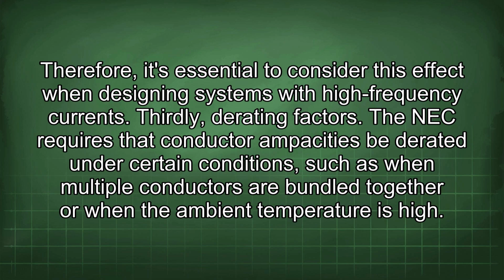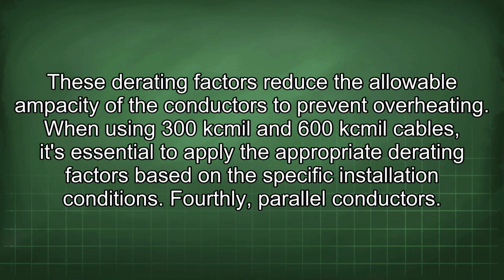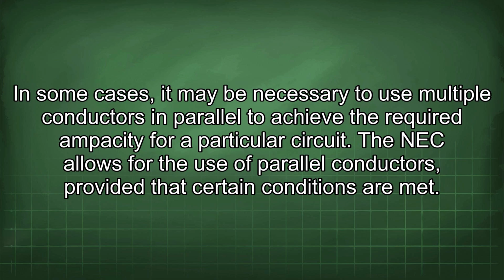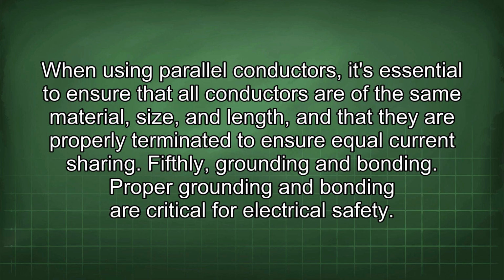Thirdly, derating factors. The NEC requires that conductor ampacities be derated under certain conditions, such as when multiple conductors are bundled together or when the ambient temperature is high. These derating factors reduce the allowable ampacity of the conductors to prevent overheating. When using 300kcmil and 600kcmil cables, it's essential to apply the appropriate derating factors based on the specific installation conditions. Fourthly, parallel conductors. In some cases, it may be necessary to use multiple conductors in parallel to achieve the required ampacity for a particular circuit. The NEC allows for the use of parallel conductors, provided that certain conditions are met. When using parallel conductors, it's essential to ensure that all conductors are of the same material, size, and length, and that they are properly terminated to ensure equal current sharing.